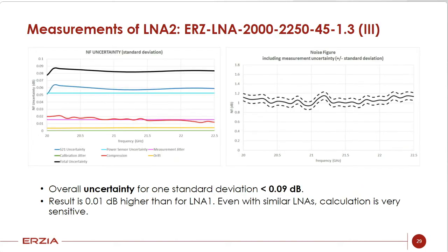As done with the first case, we have calculated the uncertainty with 1 sigma. The overall value is below 0.09 dB. Of course, this is a negligible difference, but there is a difference of 0.01 dB between LNA1 and LNA2. This proves that the calculation is taking into account all the different parameters in the setup and in the DUT performance. So in this case, for example, we have a higher gain and also a different input matching, and we can see the effect of this in the final result. On the right graph, we can see the noise figure, including the plus minus sigma uncertainty.